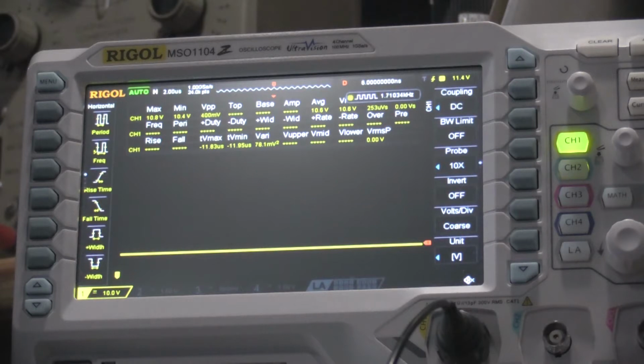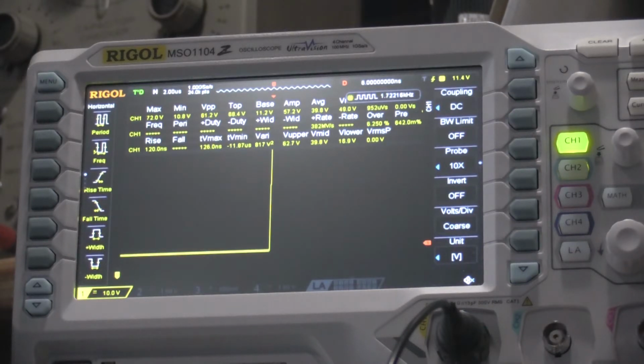Check our baseline. We're at 10.4. All the way up. Give it a little more. I'd say this probably has the factory calibration on it, because that's close enough where, with the equipment of the day, that's probably where it fell out. So this is very, very close in spec.